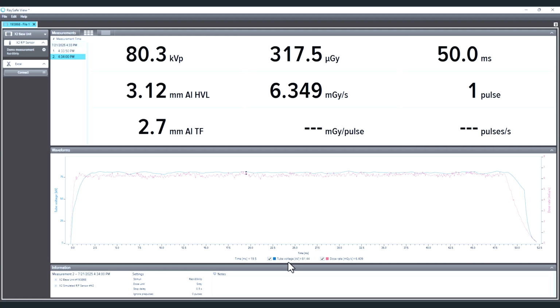You can do some basic analysis on the base unit, but more in-depth analysis is possible here. Let's say I want to establish a region of interest. I'll hit the shift key to create one, and now it shows the duration, start time, stop time, min and max and average KV, and the min, max, and integrated sum of the dose. Now if I hit escape, I'll clear that out.